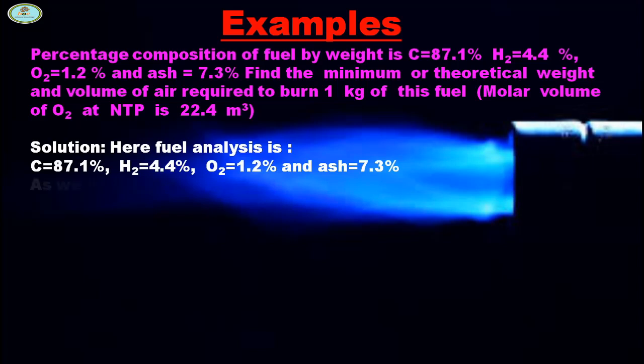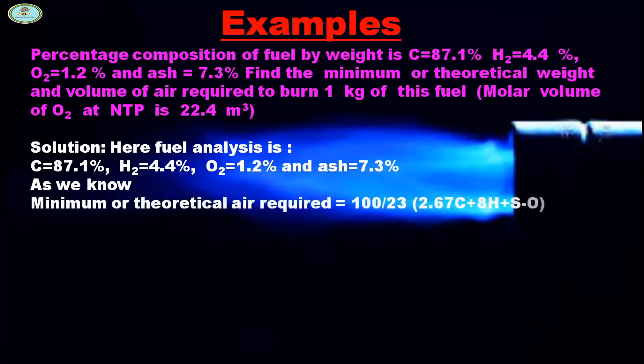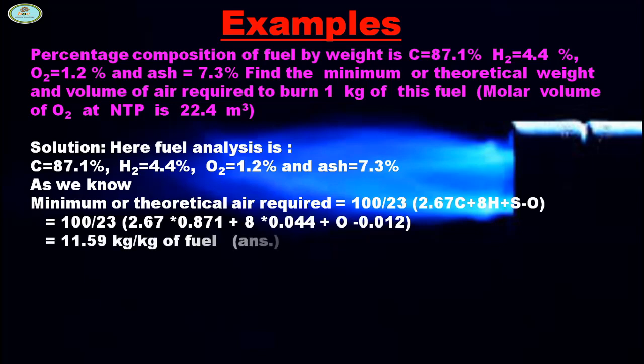Here fuel analysis is: C = 87.1%, H2 = 4.4%, O2 = 1.2%, ash = 7.3%. As we know, minimum or theoretical air required is 100/23 × (2.67C + 8H + S - O). Putting all the values, we found that air required is 11.59 kg per kg of fuel.